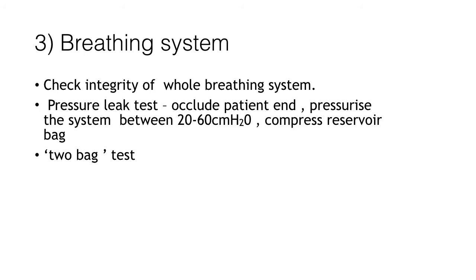Finally you also need to do the two bag test. The two bag test is a test that you should do after you have checked the breathing system, the vaporizers and the ventilator. So I shall talk about this a little bit later once we have discussed the other elements.